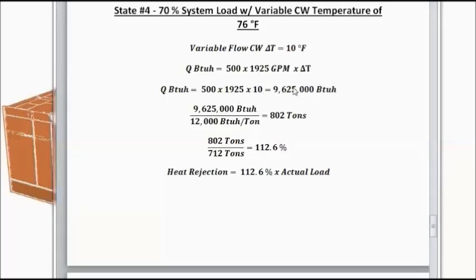Now, when we calculate our heat rejection rate, we see it at 802 tons. And over the actual load, the heat rejection rate is 112.6% of the actual load. Now, this heat rejection rate compared to the previous changes is fairly significant. And I'll show that now with some additional calculations.